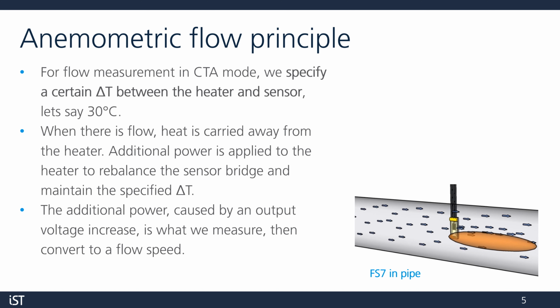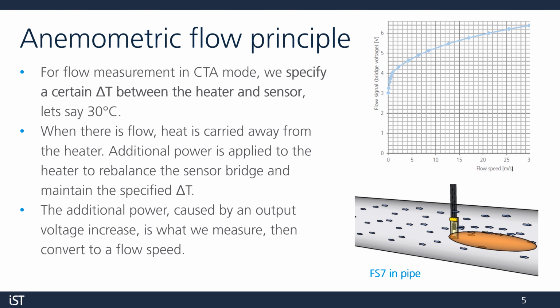Like I mentioned before, we specify a certain temperature difference between the heater and the sensor. For example, let's say it's 30 degrees Celsius. When there is flow, heat is carried away from the heater, and additional power is applied to the heater to rebalance the sensor bridge and maintain the specified temperature difference. This additional power, caused by an output voltage increase, is what we measure. This is then converted to a flow speed.